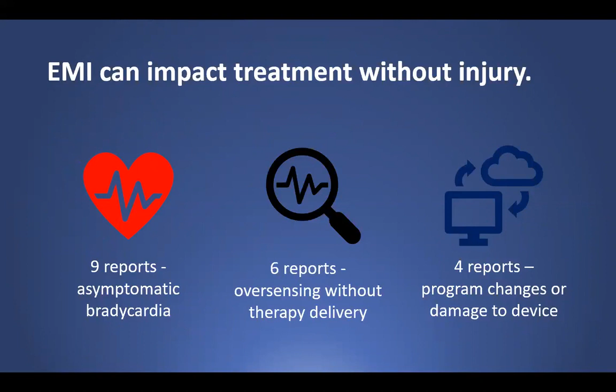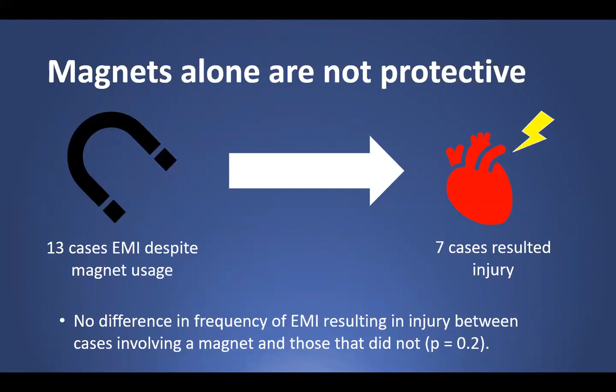A magnet is frequently placed to change the CIED settings in the setting of a procedure, and is a common safety measure taken to prevent adverse events due to EMI. However, 13 of the 45 cases occurred despite the use of a magnet, with 7 of those resulting in injury. There was no difference in injury frequency in cases that involved a magnet versus those that did not, however. Now, concerningly, episodes of EMI appeared to increase over the length of study duration, with most recent years having the highest rate of recorded episodes.